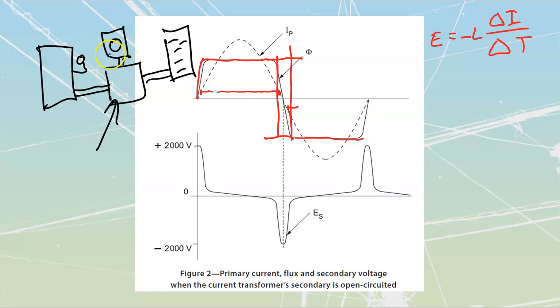There's a massive danger here, because that CT is still in place. It's still passing current through from one side to the other, and my CT windings are going around that, feeding up into the meter. So what I'm doing by pulling the meter is opening that secondary, not actually interrupting the load itself.